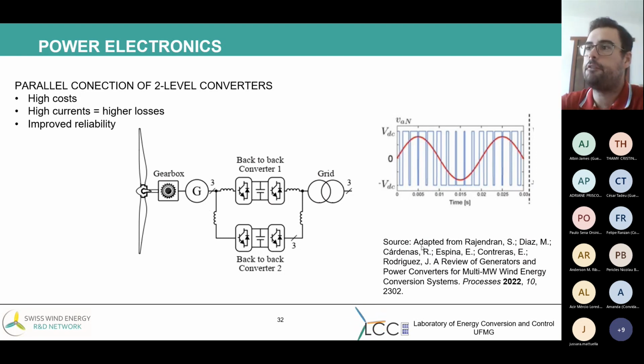So when I have offshore applications, I have machines with higher power. So I need systems with higher currents, higher voltages. So it's necessary to use different types of converters. One way to increase the power of the converter is, instead of having only one converter, I have two converters in parallel. In this type, I also need a filter to filter the grid connection. Sometimes I also need one on the generator side to make this parallel connection possible.